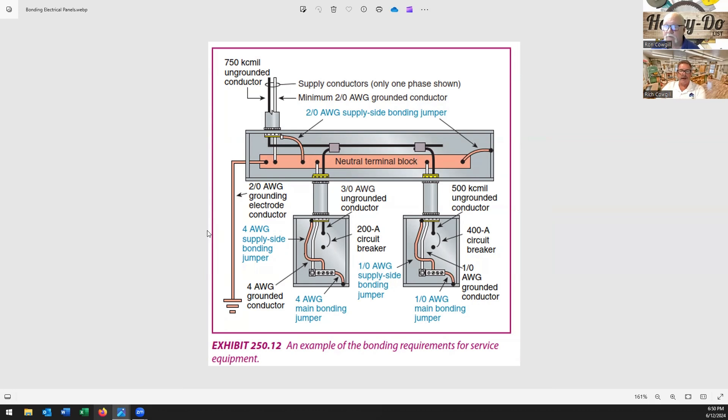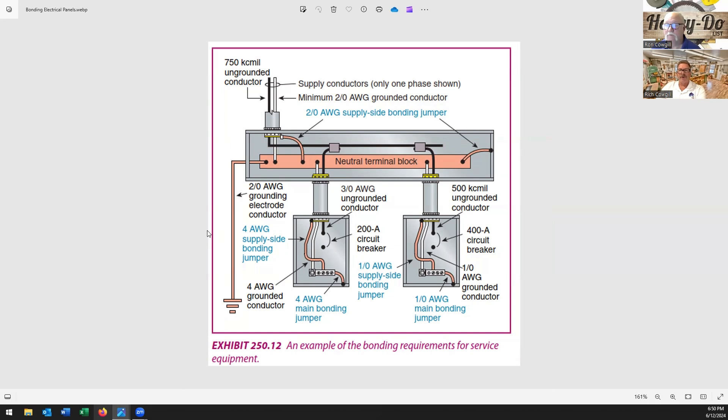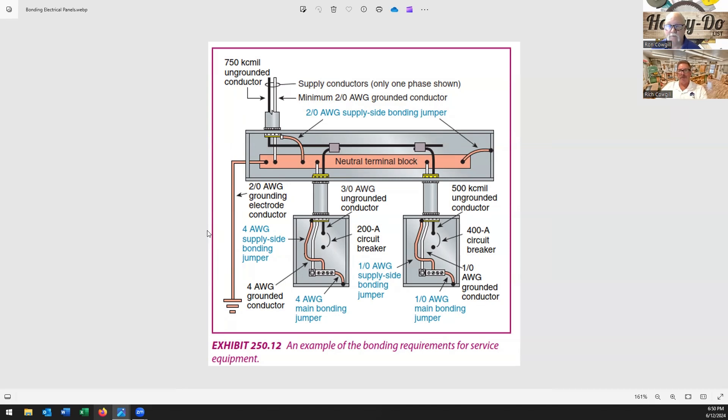When I learned about bonding I was actually building a job in Burr Ridge and I had an electrical inspector fail a bathroom inspection because my whirlpool tub was not bonded to the drain. And I had never done that before and I asked him what's - I don't understand what's the point of this. And fortunately it was a good inspector, or at least I asked the question properly. And he explained to me that because the drain is brass, my water line is copper, there's chrome on top of that - brass and copper do not carry electricity at the same potential. There's a variance in how much electricity will flow.